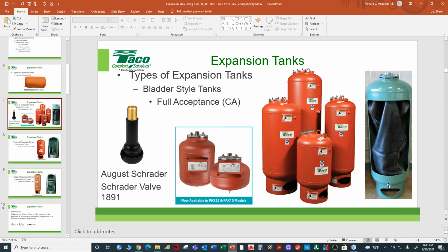When you get an expansion tank, before you connect it to the system, there is no fluid inside the bladder. And if it did not leak air, there should be a minimum of 12 pounds on the air side. So there's no fluid in the tank. The only way that fluid gets into the tank is once you properly pre-charge the air side, then you connect it to the system. And if the system pressure is equal to the air charge, the fluid does not enter the tank. The air is 40 pounds in our example. The water minimum pressure is 40 pounds. The water will not enter the bladder.